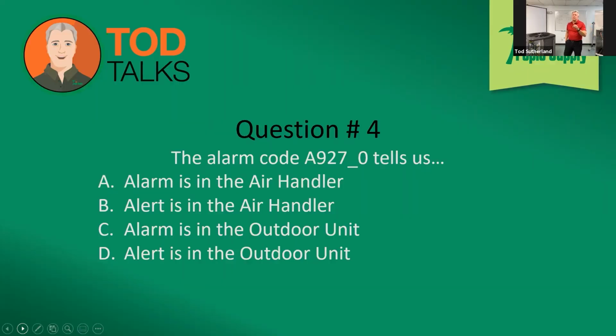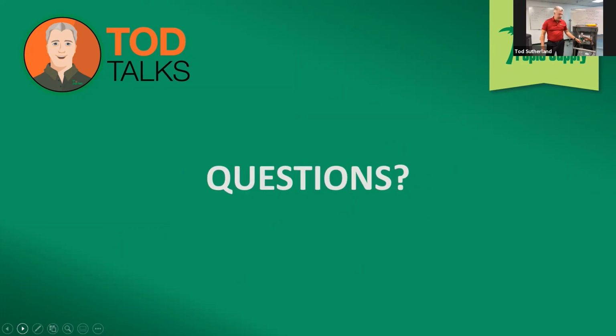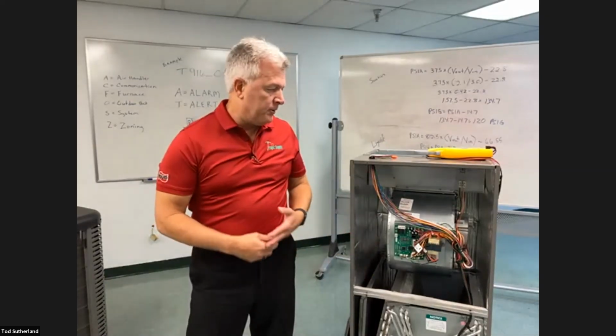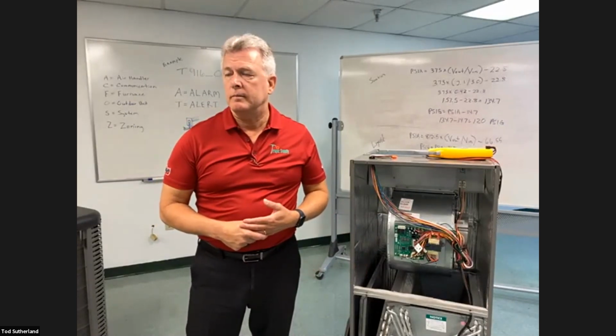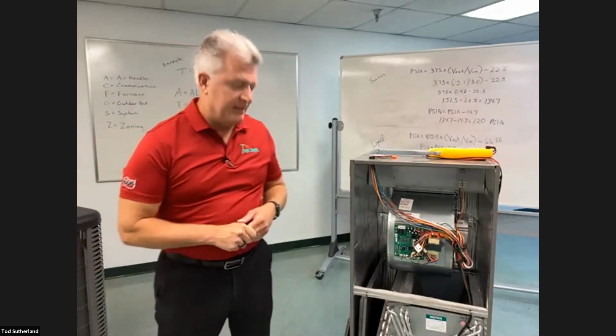Okay, and while we were talking a second ago about the pressure transducers, keep in mind that this pressure transducer plug that we had on the air handler, that's your red, green, and black wire, that pressure transducer can be popped off of that valve and interchanged with the one that's in the outdoor unit as well. So there's a lot of common parts that are used on these. When you're out in the field trying to troubleshoot and get a system up and running, mainly on the heat pumps, because we don't have a lot of the same on the straight cool units, if we were having a problem with the wiring on this pressure transducer, we could pull the one off of the outdoor unit and move it to the indoor unit. Same thing with the stepper motor. Is there a Schrader valve on that pressure transducer? Yes. There better be. Yes, there is.